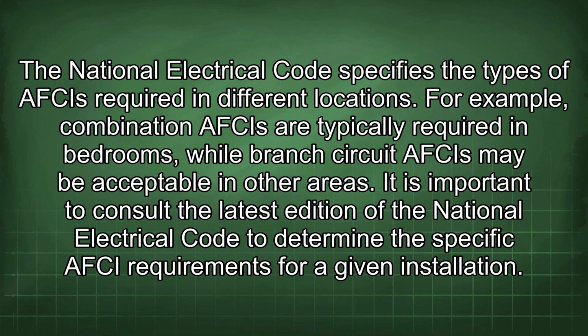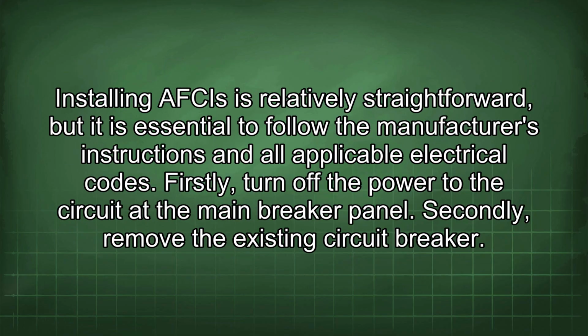The National Electrical Code specifies the types of AFCIs required in different locations. For example, combination AFCIs are typically required in bedrooms, while branch circuit AFCIs may be acceptable in other areas. It is important to consult the latest edition of the National Electrical Code to determine the specific AFCI requirements for a given installation. Installing AFCIs is relatively straightforward, but it is essential to follow the manufacturer's instructions and all applicable electrical codes. Firstly, turn off the power to the circuit at the main breaker panel.